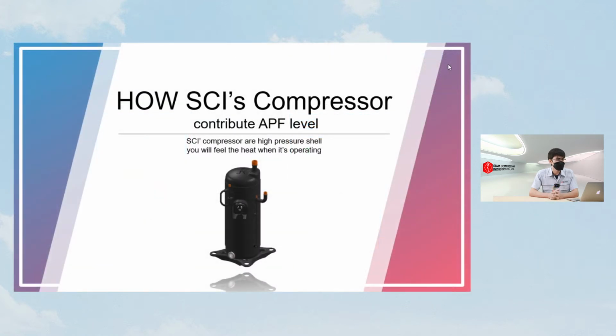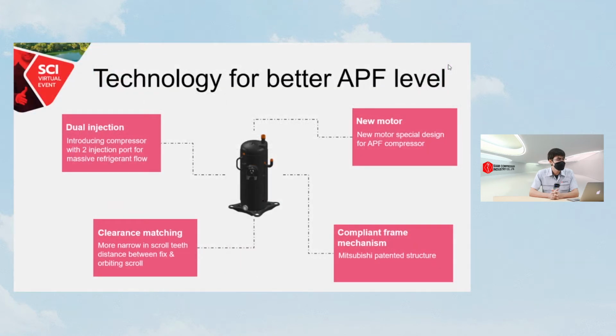But how does a compressor contribute to getting you a better APF standard? Keep in mind that our compressor is a high pressure shell. You may feel the heat when it's operating. And here is the technology that can bring you a better APF standard. The first one is the new motor design. We have a new motor design that's special for the APF compressor.